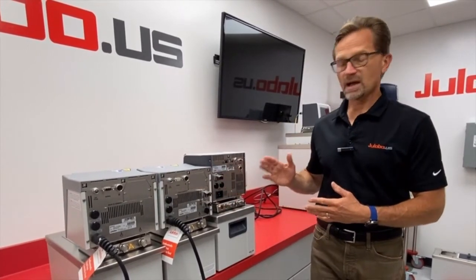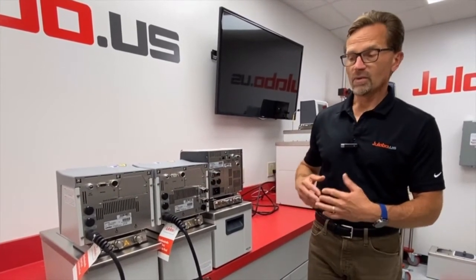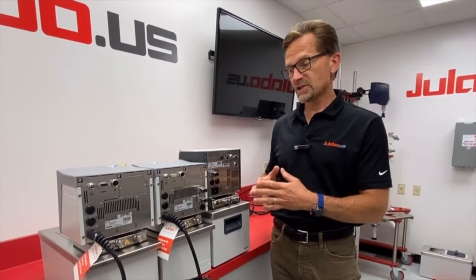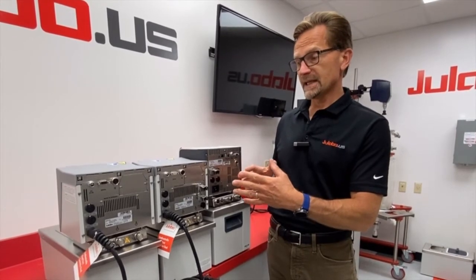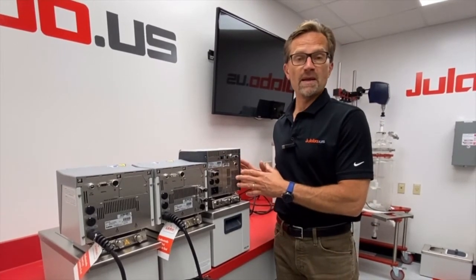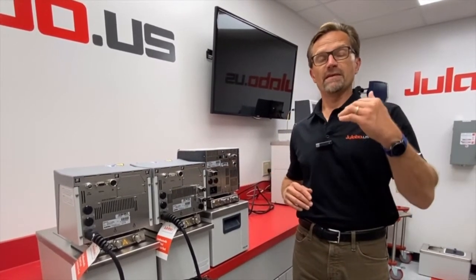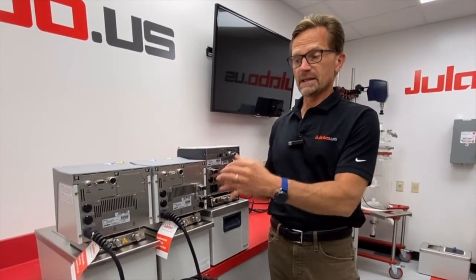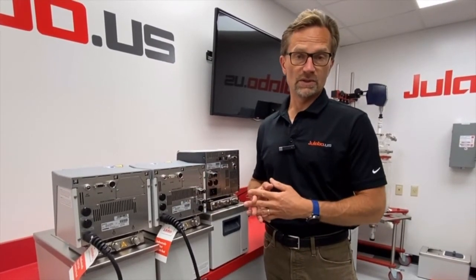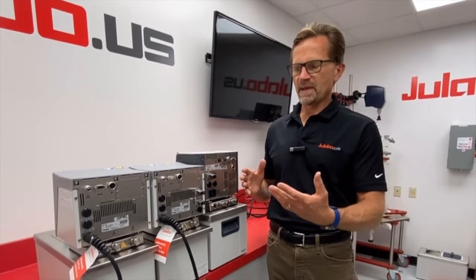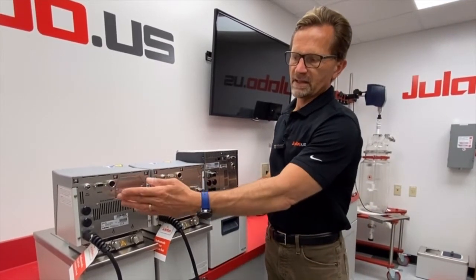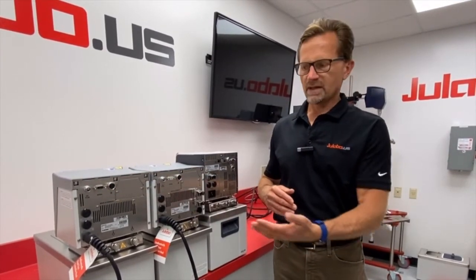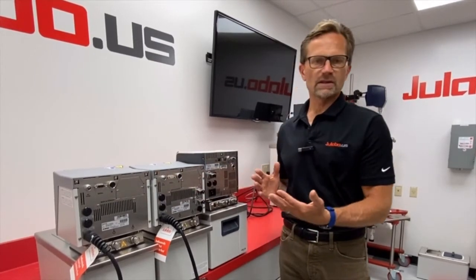So now that we've gone through the features and some of the comparisons between the HighTech HE/HL models and the new MAGIO MS circulator, when would you choose one over the other? If you have a high temperature application near 250 degrees C, you probably want to go with the MAGIO MS because it has an upper limit of 300 degrees C, whereas the HE and the HL can only go to 200 degrees C. So from an I/O perspective, if basic RS-232 is fine for you, well then maybe an HE or any of these models can work for you.